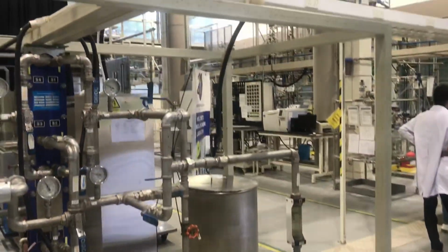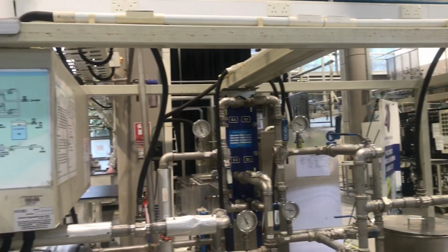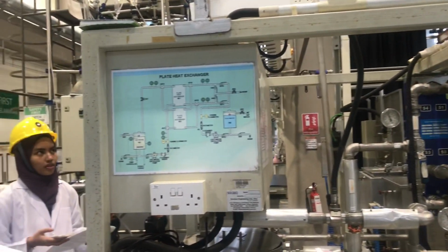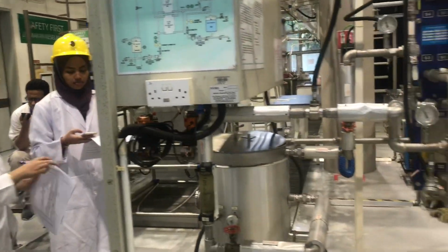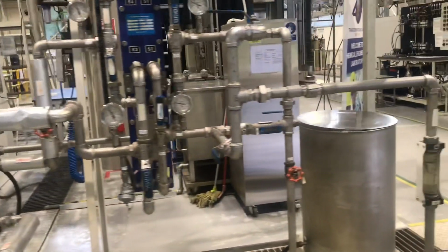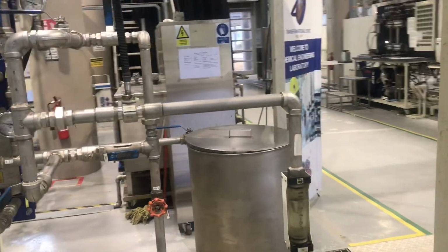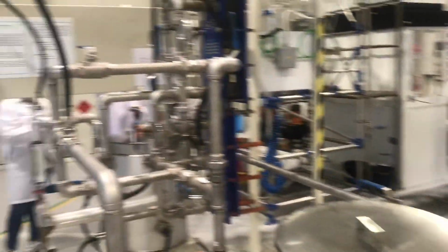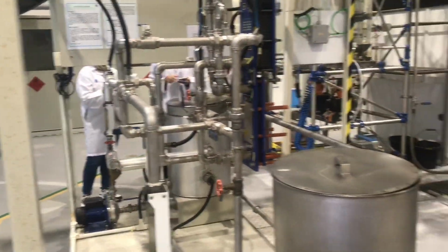The HE200 comes with Alfa Laval plate heat exchanger and two stainless steel sump tanks for the hot and cold water supplies. The hot tank is fitted with 3-4.5 kW tubular immersion heater that are protected against possible overheating. Each tank is equipped by a centrifugal pump capable of delivering 20 liters per minute of water.